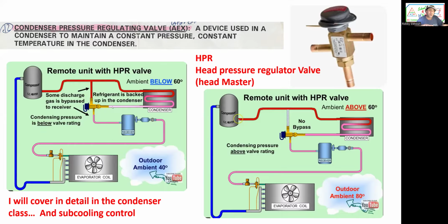So we'll cover the headmaster, the head pressure regulator valve, again in great detail when we talk about condensers, and when we talk about subcooling control, since there's more than one way to control subcooling. And how to know when it's full, when there's enough to charge. I had a couple of problems before. I thought I had a leak because it was low in freon, but it wasn't low in freon. It wasn't charged properly. It's a very big mistake people make with the HPR valve. But I'll cover it again in detail later when I do condensers. Now we have to move on.